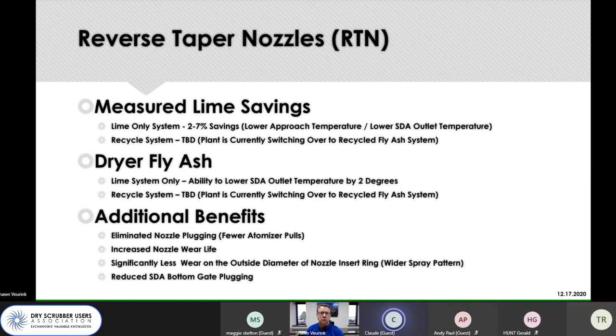With the reverse taper nozzle on lime only, we've seen quite a bit less plugging, which indicates to me we get less wetting on that wall. The fan pattern gets better contact with the flue gas as it flows through the stream and dries faster. That accounts for our drier fly ash, and we've had a lot less plugging as a result.